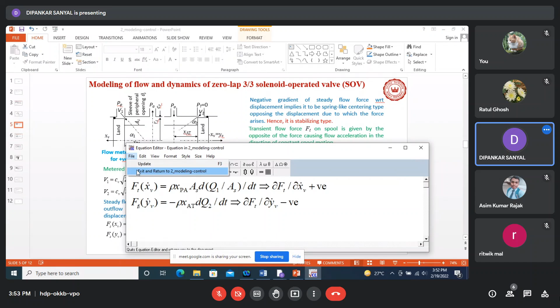When the spool is fully closed, there is no flow here. As we are opening the orifice, this velocity keeps on increasing, as a result of which the mass that flows through the valve keeps on accelerating. In order to accelerate the oil mass, we need to exert a force along the direction of acceleration, and an opposite reaction force will act on the land. That is how we have obtained the expression for the transient flow force.